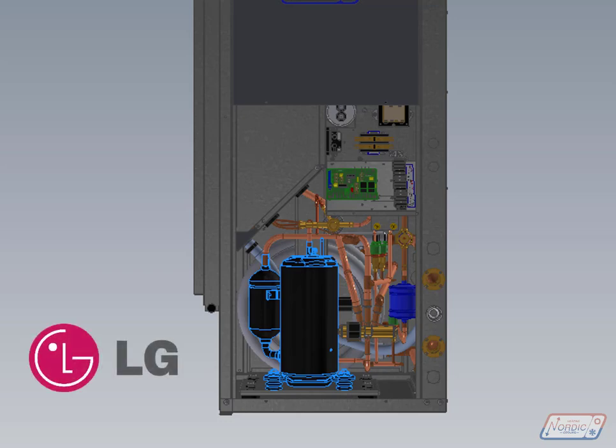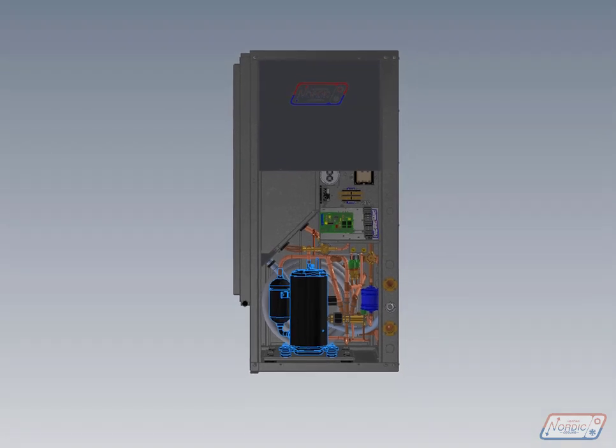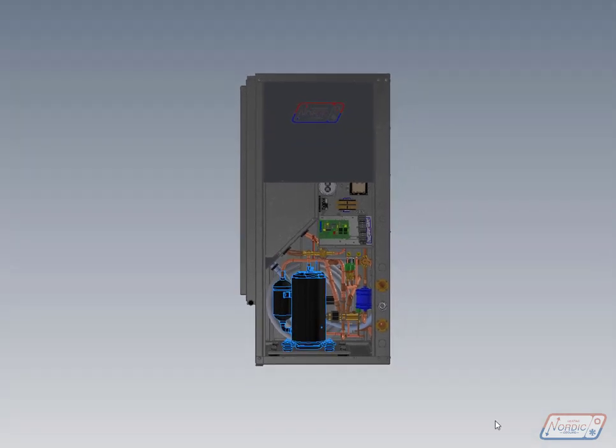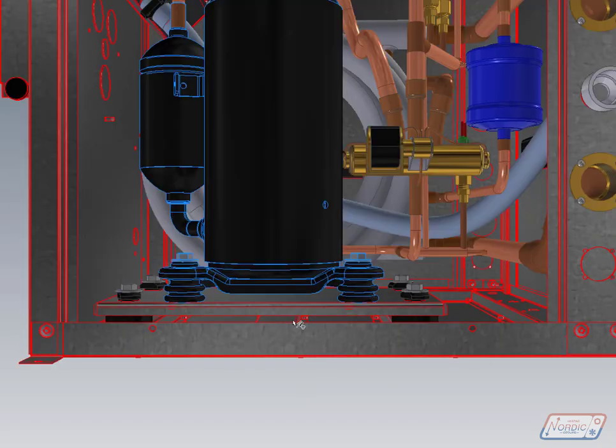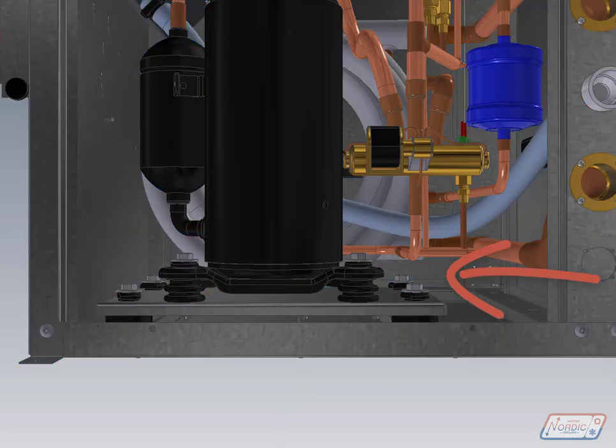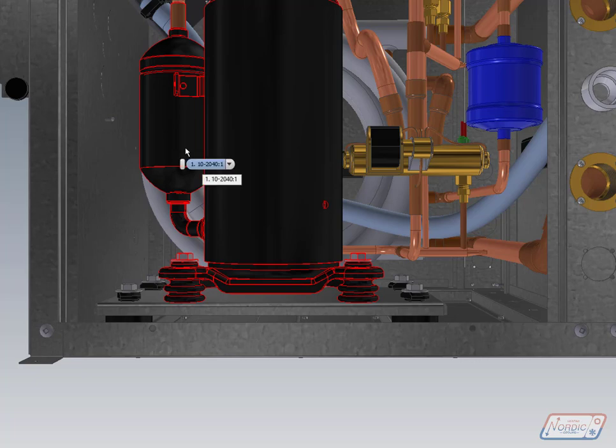And yes, that's the same company that makes smartphones and TVs and so on. These compressors are cost-effective and they're available in small sizes, but are single stage. So the small efficiency advantage you get when running on stage 1 isn't present on these units. Like in our other heat pump series, the compressor is mounted with double grommet isolation on a plate, so that's a very good noise control measure, and an optional sound jacket is also available for very noise sensitive applications. These compressors have a built-in suction accumulator for maximum protection against liquid floodback to the compressor, which is a very good feature.